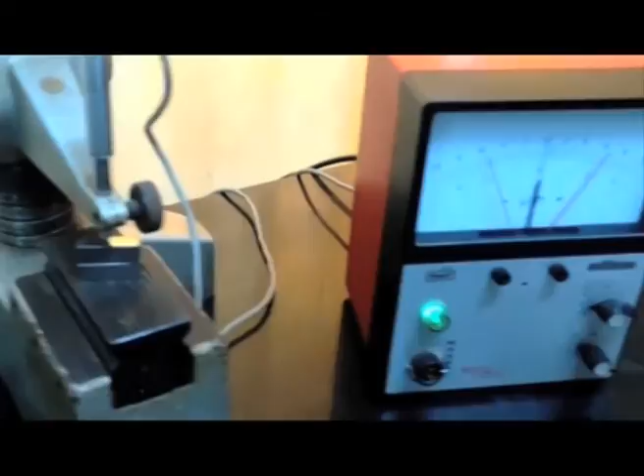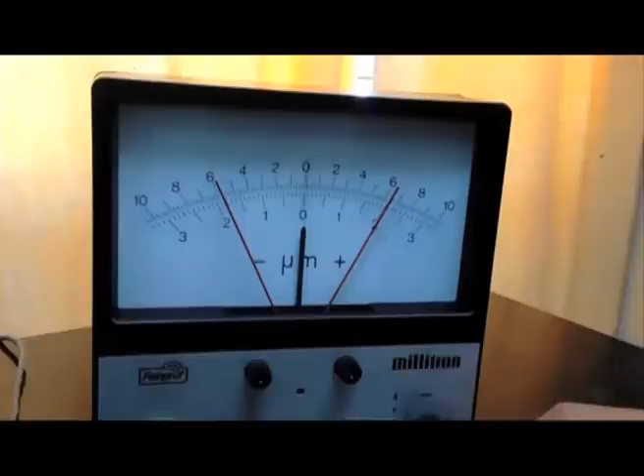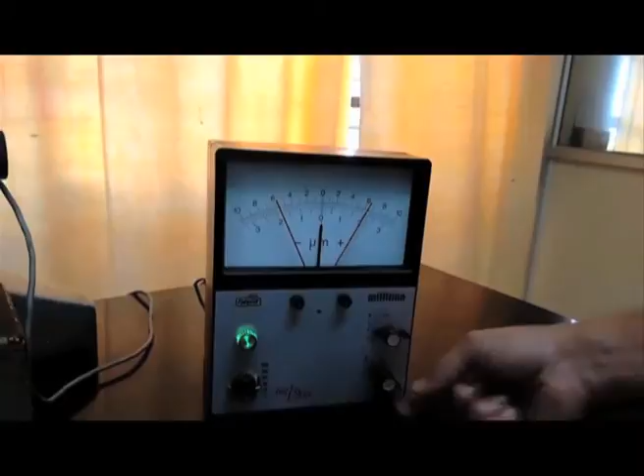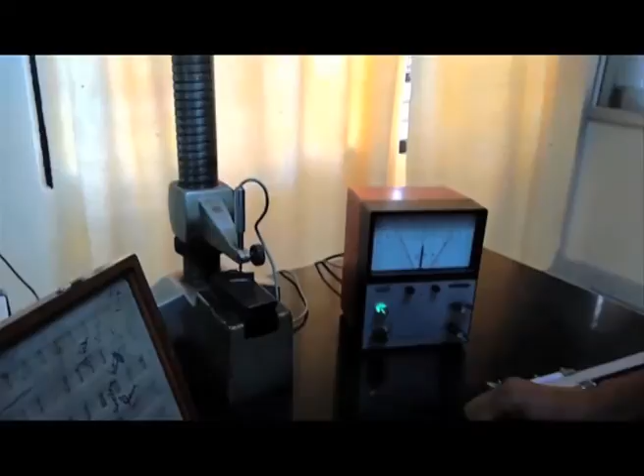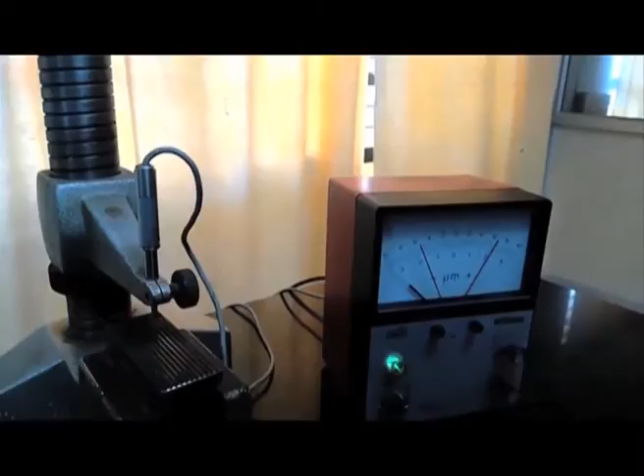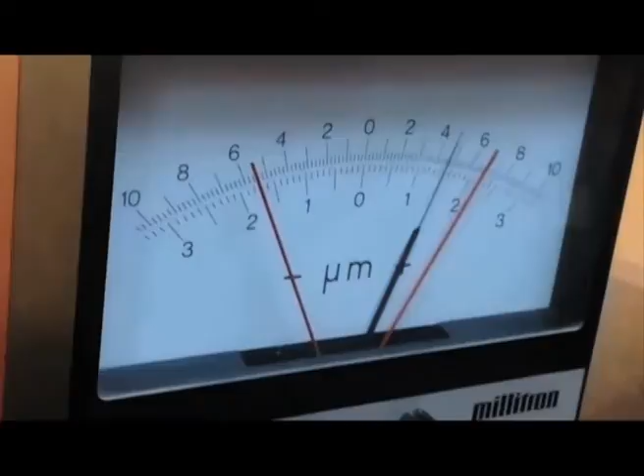Now you can see the pointer is reading 0. There is a small parallax error. Now the reading is 0. Now I'm removing the slip gauge pile, and then I'm inserting the workpiece to be inspected. Depending upon the actual size of the workpiece, the pointer will move to the positive side or negative side. If the size is greater than 19 millimeter, the pointer will move to the positive side. Now it is reading 4. We have selected the range sensitivity of 100, so we have to read the top scale.